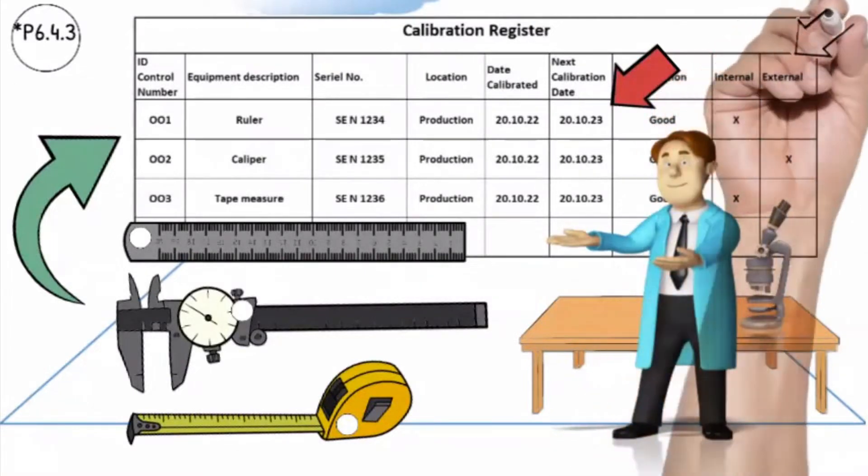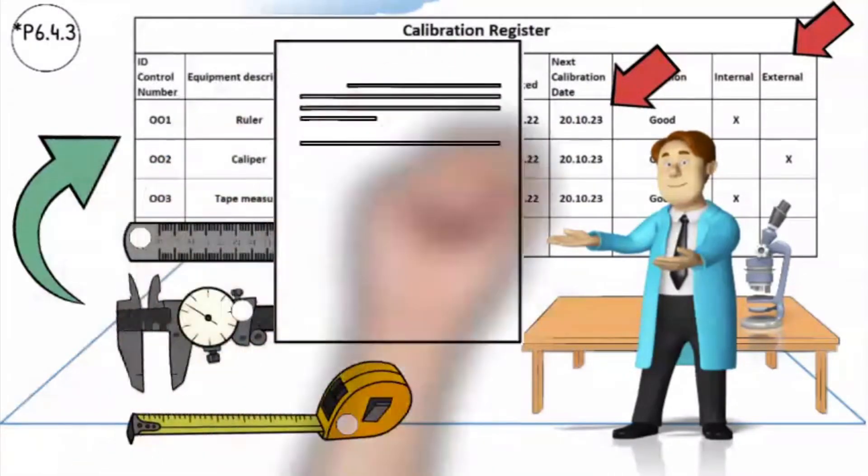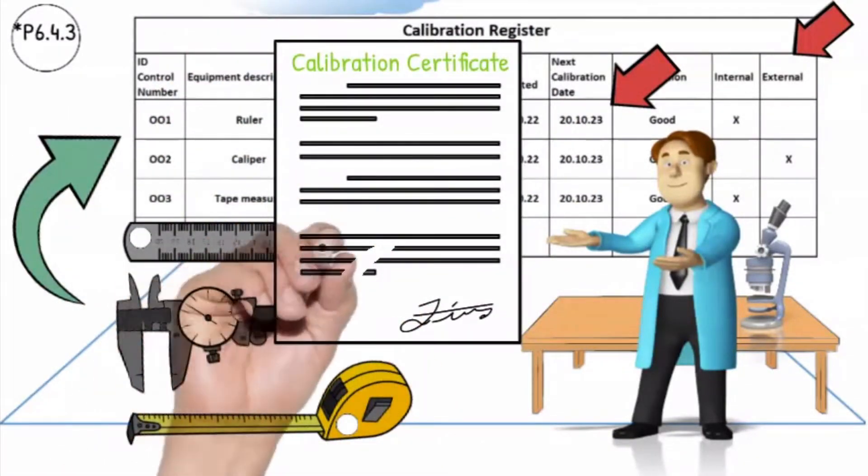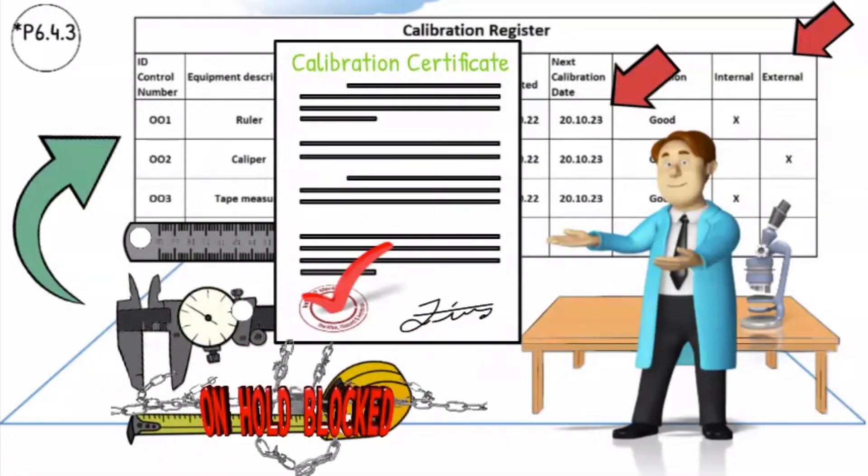The technician also has to ensure that the external laboratory is qualified to calibrate the equipment and that the calibration certificate shall include the mark of the national accreditation body. All measuring and test equipment that is out of calibration or damaged must be blocked and taken out of circulation.